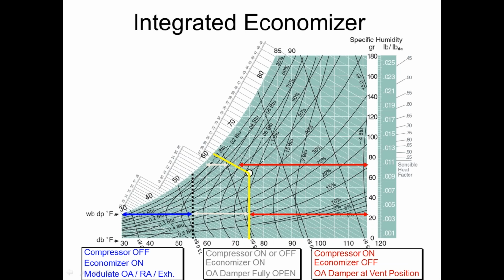When I have the integrated economizer, my psych chart might look more like this, right? So essentially, if it's below 55 degrees, I should be able to get all the cooling done with the economizer. If it's above 75, I'm going to have to use compression, right? If it's between those two, I'll probably use some combination of those two things, right? So that's why I got this extra section on my chart over here now. You probably have seen stuff like that before.